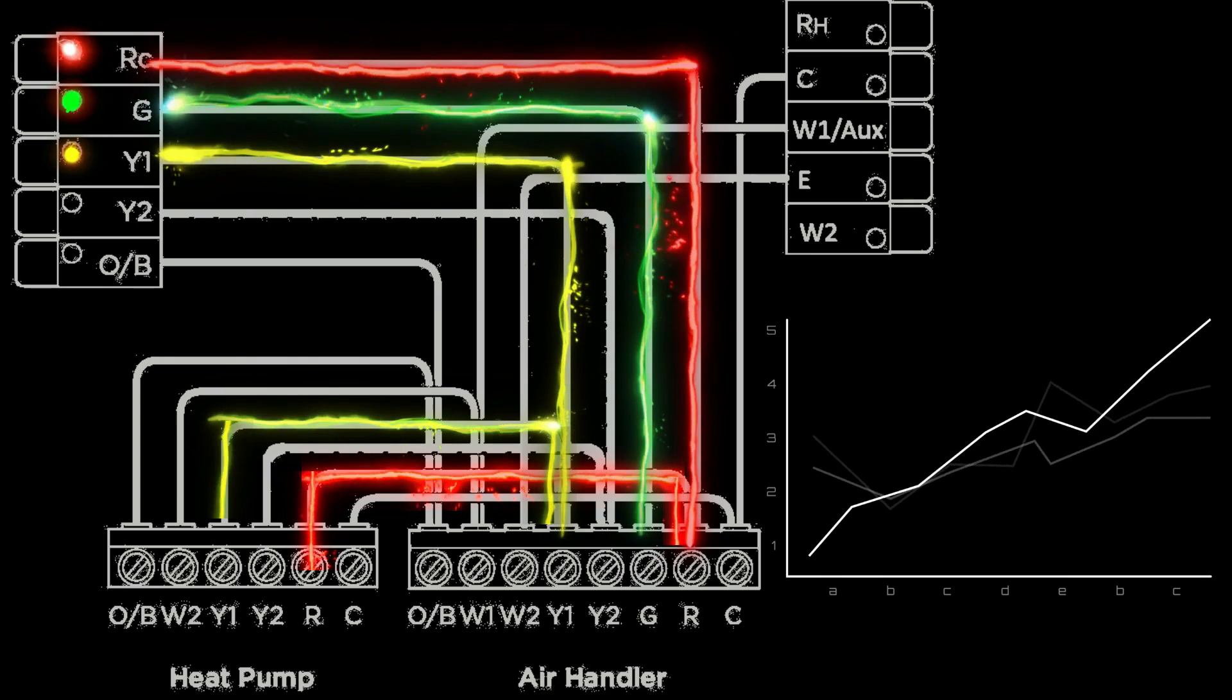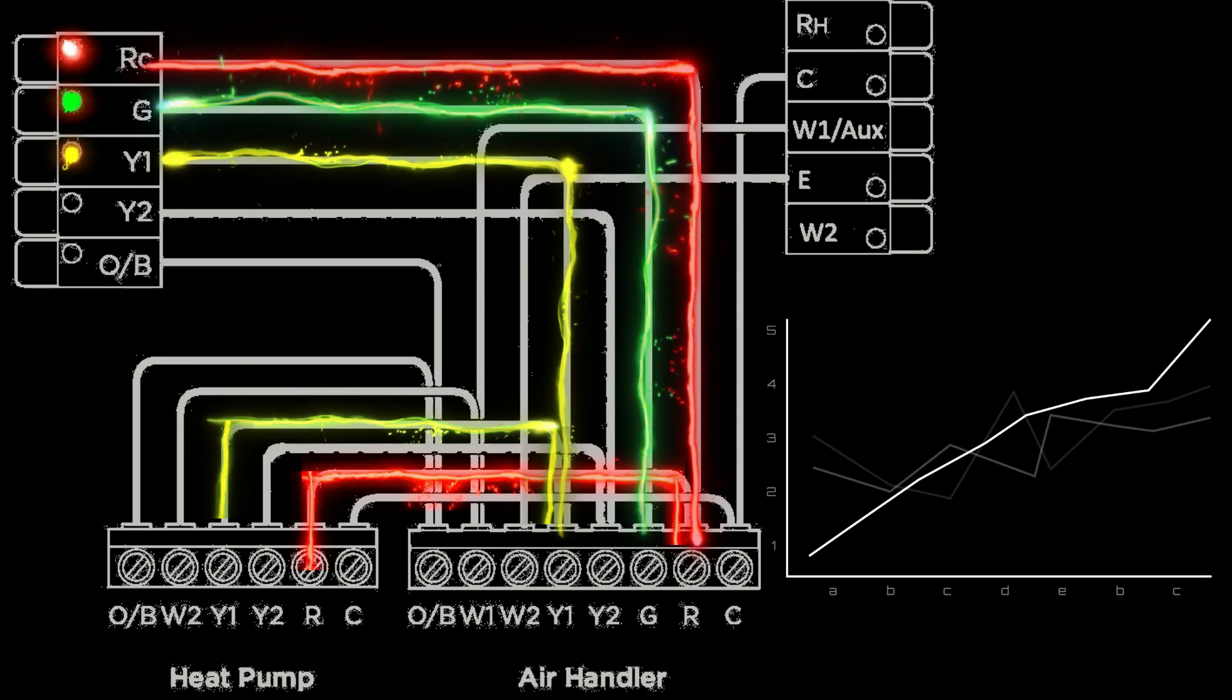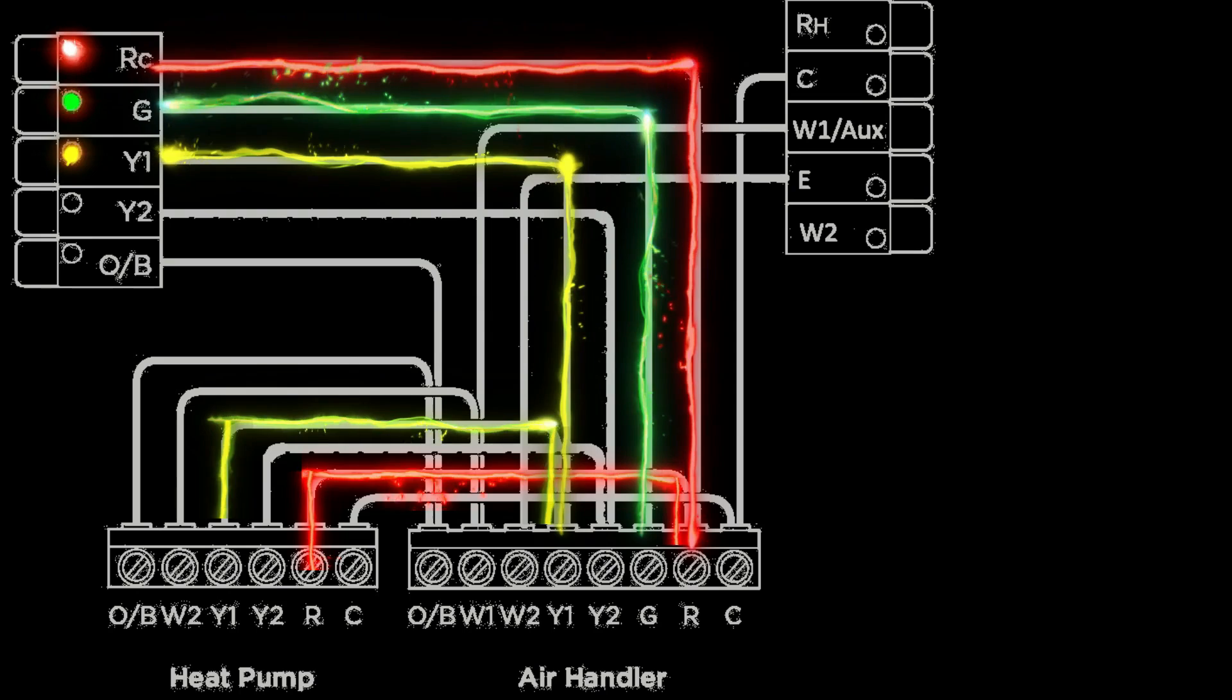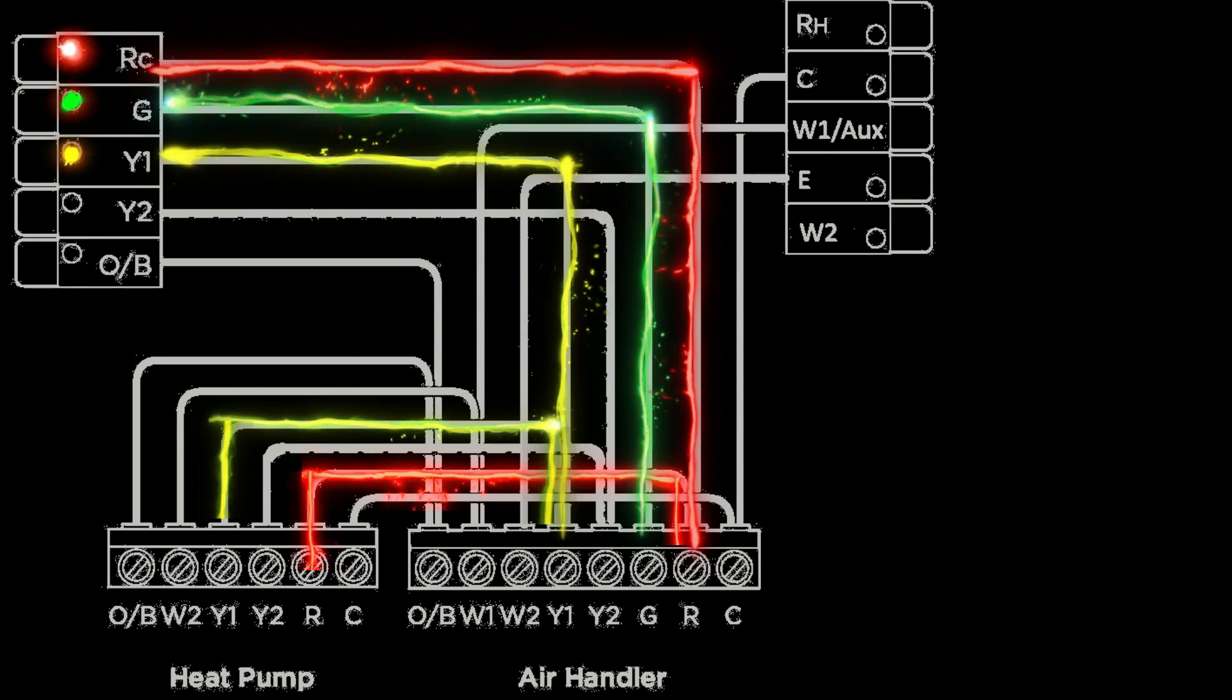Now if that temperature starts to drop out of that one degree differential it will start plotting that and looking for a pattern. As the temperature continues to drop outside of that one degree differential, the more it does that, the sooner the thermostat will start kicking in second stage.